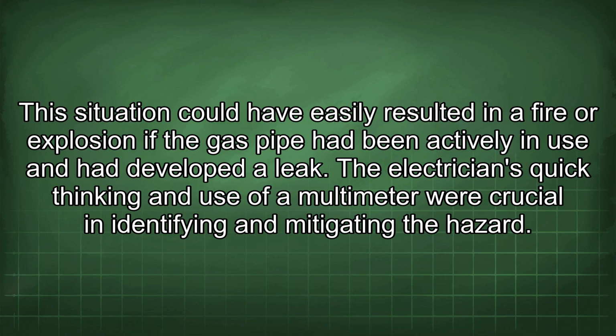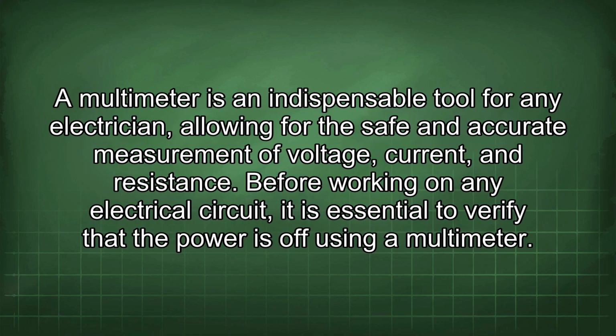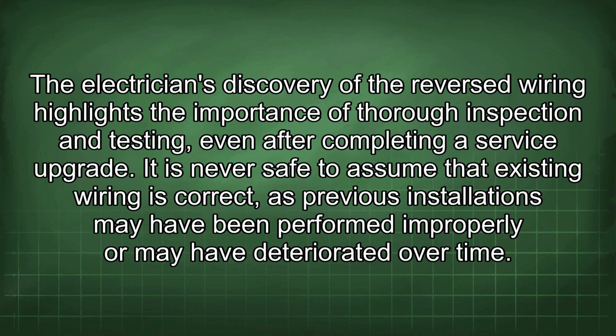The electrician's quick thinking and use of a multimeter were crucial in identifying and mitigating the hazard. A multimeter is an indispensable tool for any electrician, allowing for the safe and accurate measurement of voltage, current, and resistance. Before working on any electrical circuit, it is essential to verify that the power is off using a multimeter. The electrician's discovery of the reversed wiring highlights the importance of thorough inspection and testing, even after completing a service upgrade. It is never safe to assume that existing wiring is correct, as previous installations may have been performed improperly or may have deteriorated over time.